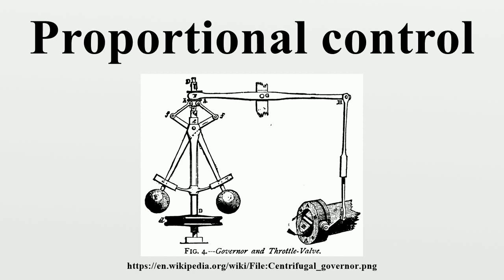Proportional control action leaves out an error called offset error. Once a disturbance occurs in the steady state condition, any corrective control action based purely on proportional control will always leave an error between the next steady state and the desired set point. This error is called an offset error.